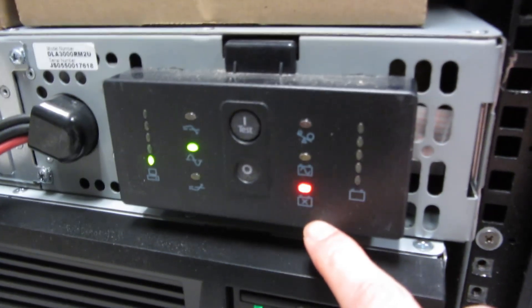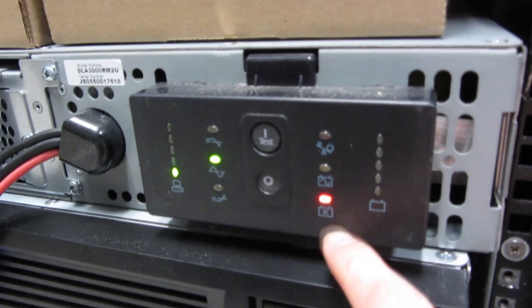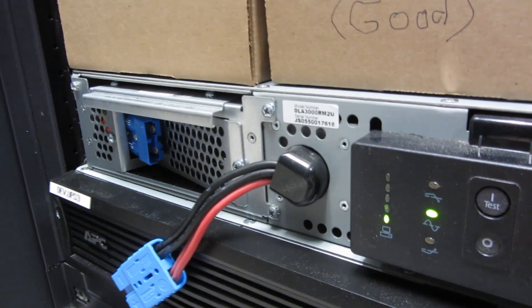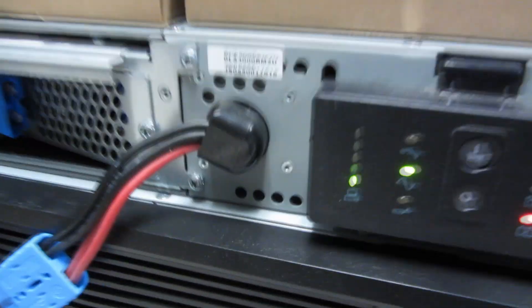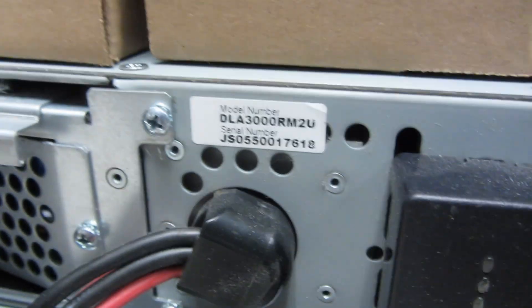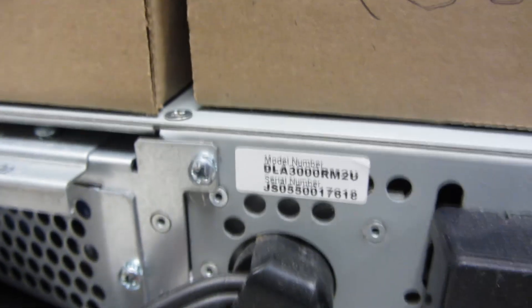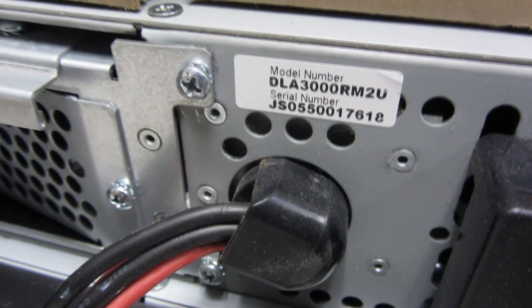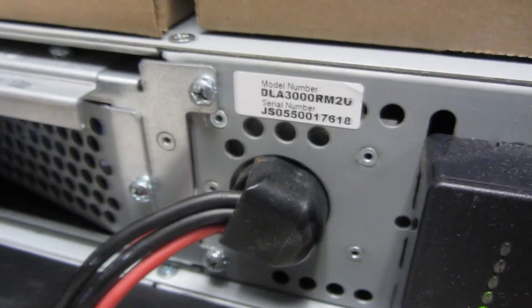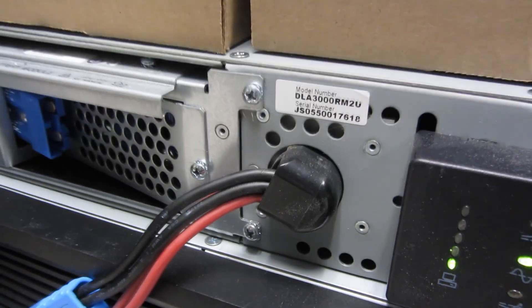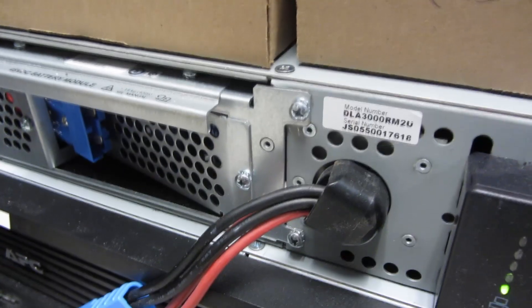Now you can see here on the panel I have this battery light blinking which indicates I have to change the battery. So I'm going to go ahead and do that. The other thing I want to show is that this is the model number, but the number for this particular battery is usually RBC 43. So that's the replacement battery and I'll have that in the description section.